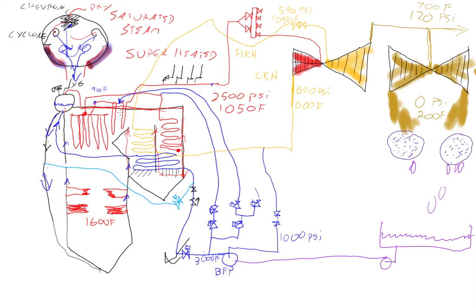The same way that when we added heat to the water and the walls and it changed to steam, it expanded and that created pressure. When we take the heat out of the saturated steam here and turn it into water, the steam collapses and it's way smaller, way more dense. As it converts from steam to water this pressure goes even lower and it pulls a vacuum.